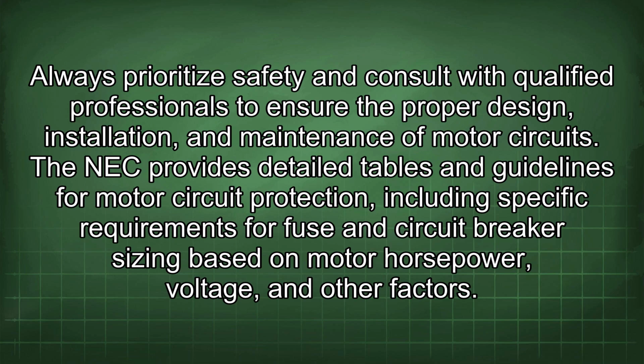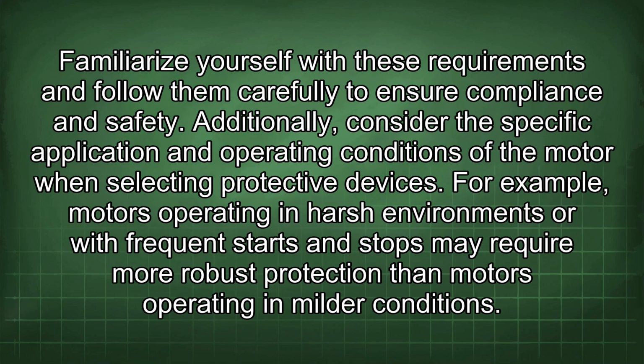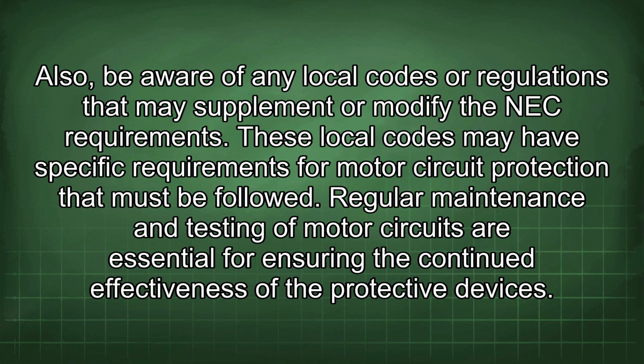The NEC provides detailed tables and guidelines for motor circuit protection, including specific requirements for fuse and circuit breaker sizing based on motor horsepower, voltage, and other factors. Familiarize yourself with these requirements and follow them carefully to ensure compliance and safety. Additionally, consider the specific application and operating conditions of the motor when selecting protective devices. For example, motors operating in harsher environments or with frequent starts and stops may require more robust protection than motors operating in milder conditions. Also, be aware of any local codes or regulations that may supplement or modify the NEC requirements. These local codes may have specific requirements for motor circuit protection that must be followed.